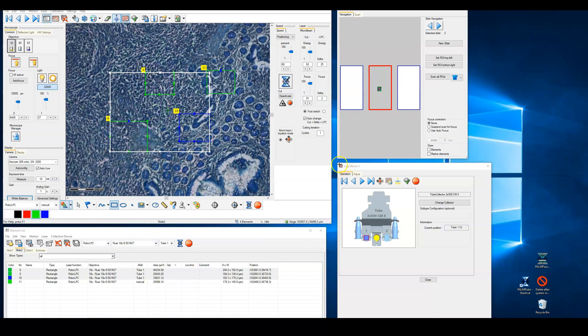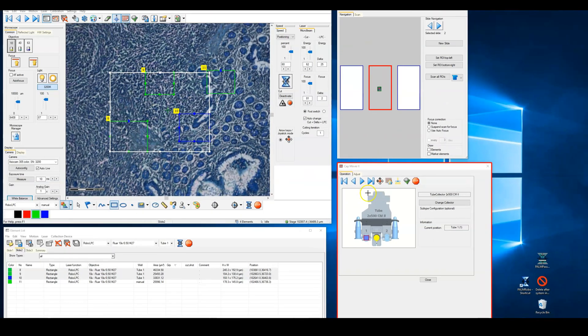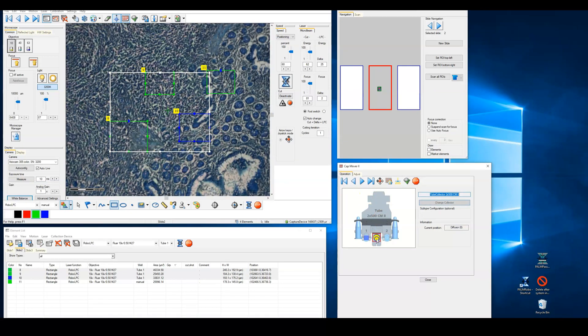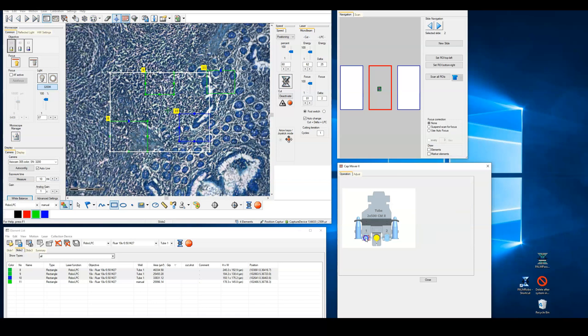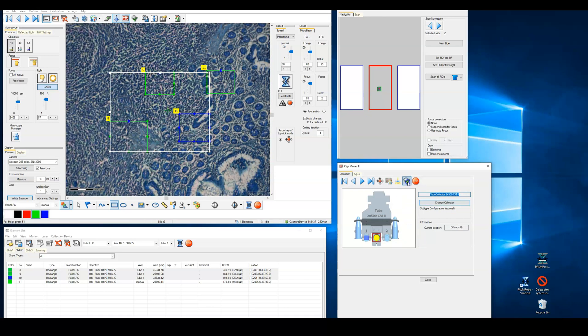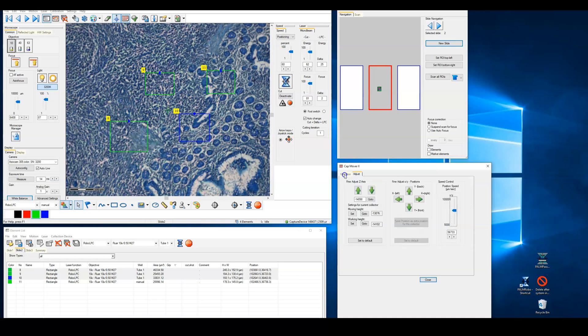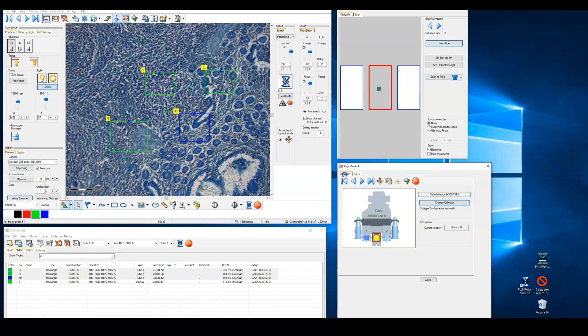We've already used the collector window and have seen how we can select the different capture devices by clicking on the graphic. Because moving the capture cap into place changes the optics of the light path, there is also a diffuser element that can be used to mimic the effect of a capture device. This is the central yellow circle. While it's not necessary to use this, it will give you a more representative image. The check cap button has been described, and there is a button to return the capture device to the home position. This stop allows us to cancel all functions of the capture device, largely as a safety measure. The capture device may be positioned further manually using these other controls, but this should not be necessary and should not be attempted when initially learning to use the system.